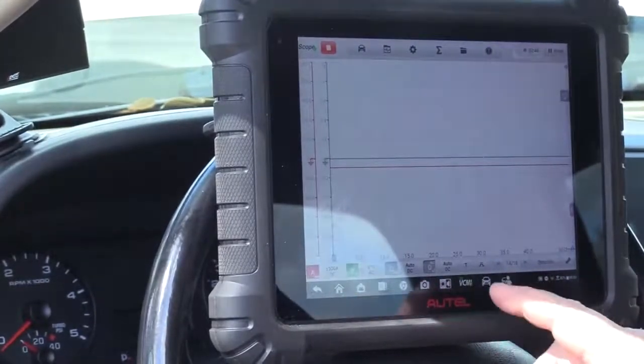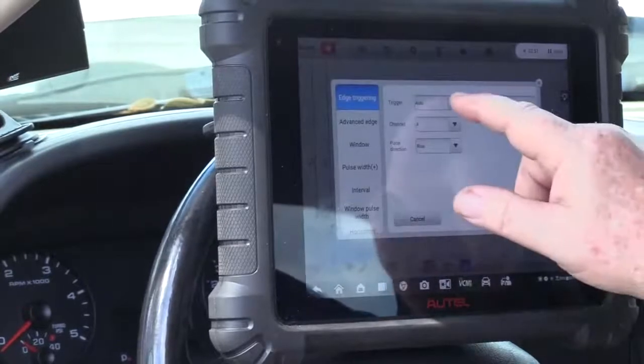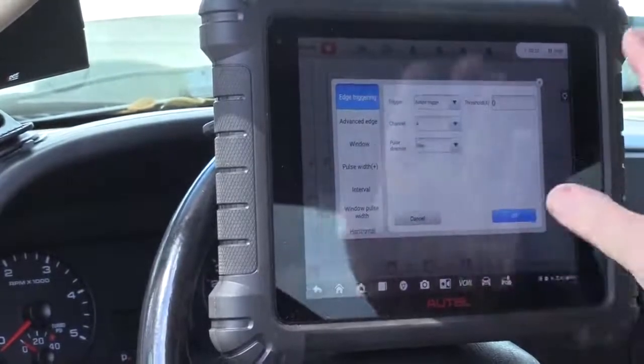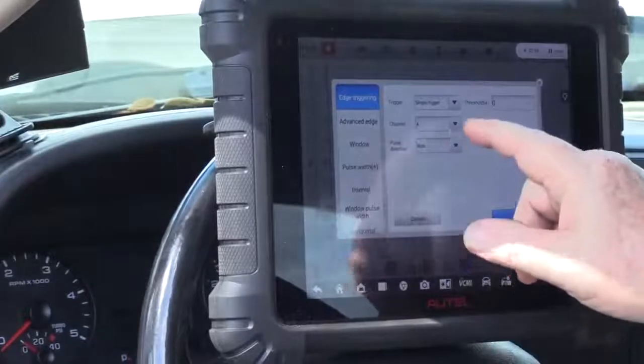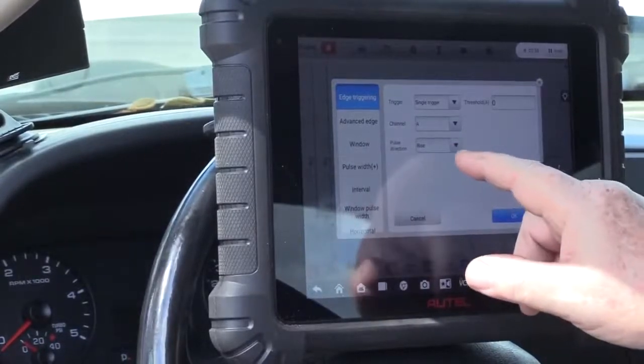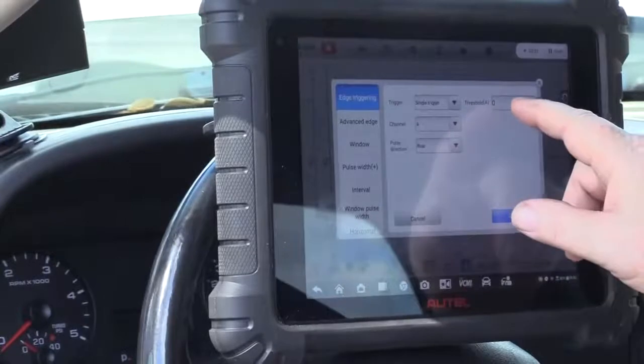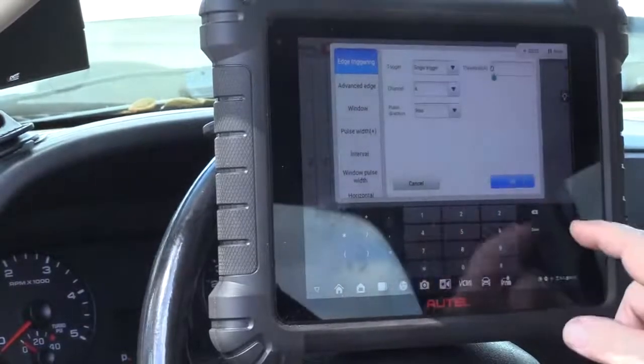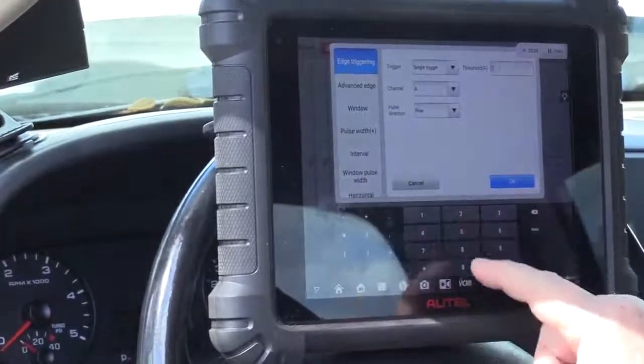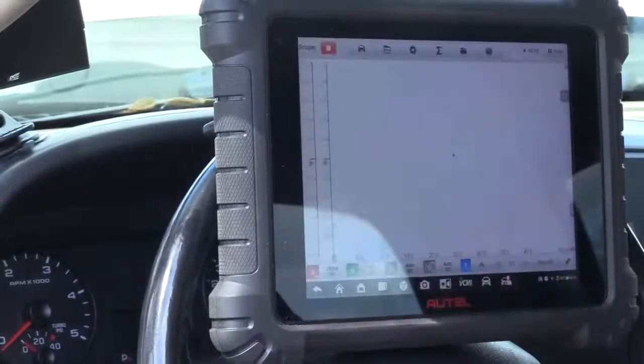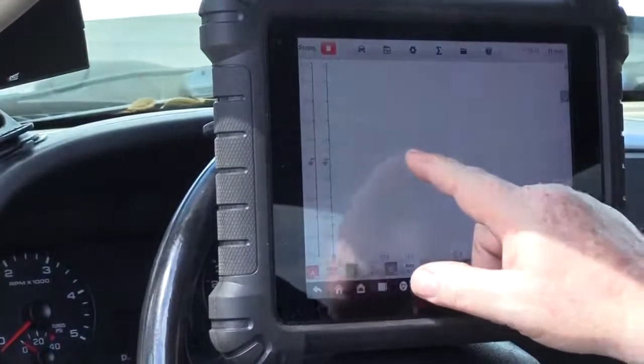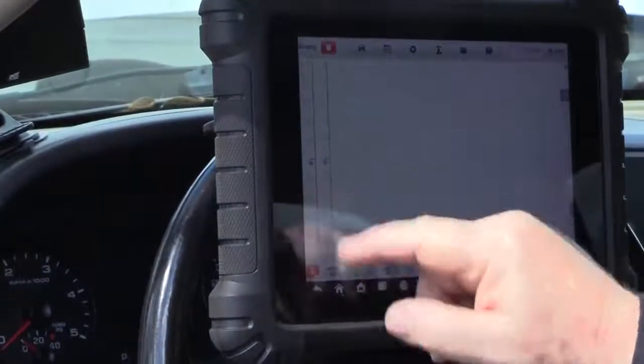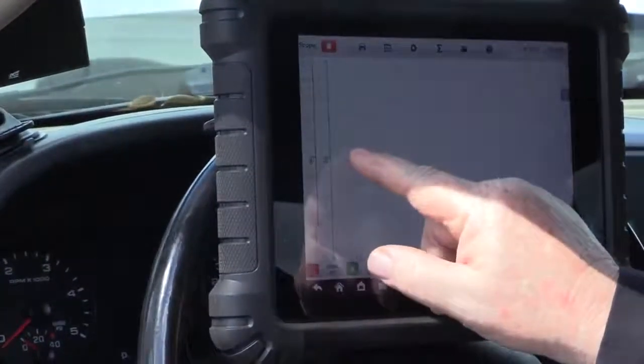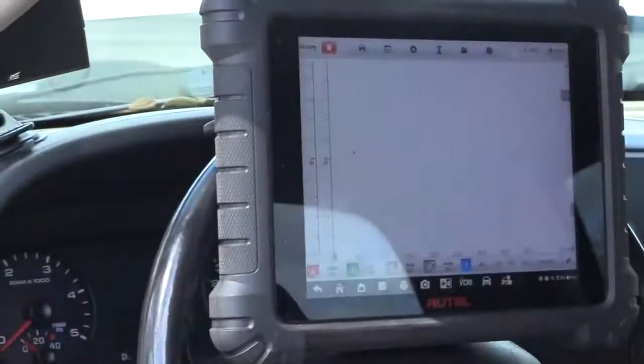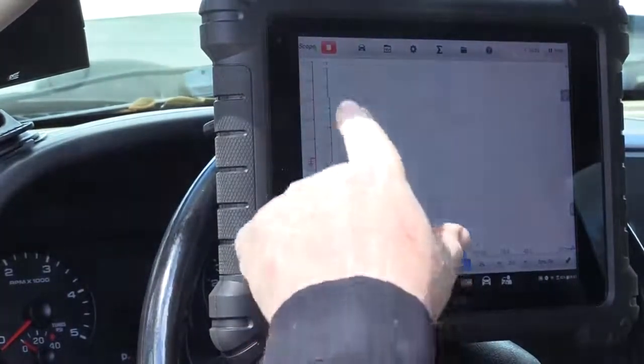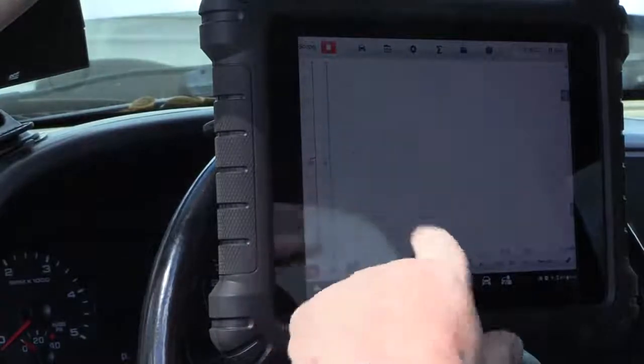And now we need a trigger. So we'll select the trigger base. I'm going to use a single because I want it to stop when it fills the screen. We'll stick with channel A, the amp probe, and use a rising pulse direction, rising trigger. And let's just set that for 10 amps. All right, you can see that we have a dot. I'm going to move that over to this side of the screen a little bit, so we get it started over on that side of the picture. I'm going to leave the voltage where it is.